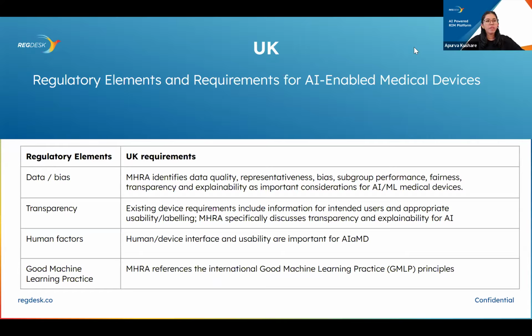So currently the UK MDR 2002 classification rules, as I mentioned, apply to both AI and software as medical devices. MHRA has identified that the current rules may not proportionately reflect the risk posed by SaMD and is developing some reforms to introduce more risk-proportionate classification. So it is still under development, and we will have some more information on that as the agency releases and updates their guidance documents. So MHRA, US FDA, and also Health Canada, as we are aware, have jointly identified 10 guiding principles that can inform the development of good machine learning practices. So we will talk a little bit more in the further slides.